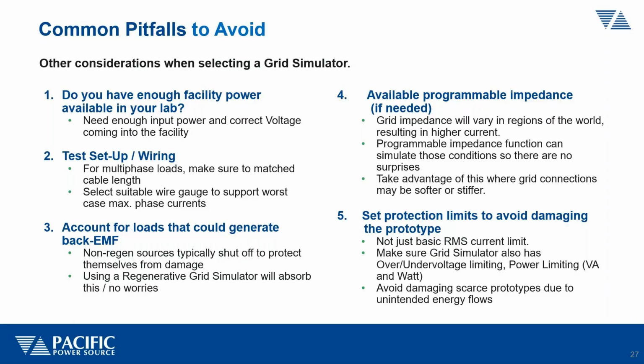Programmable impedance is a function often used in conjunction with grid testing, so you can look at different grid impedance conditions that may exist around the world. You can do that with a programmable impedance function more easily than having to insert different physical lumped impedances, which is an alternative, but less convenient and less practical. So it's easier to have programmable impedance for that purpose. And finally, protections can be important.